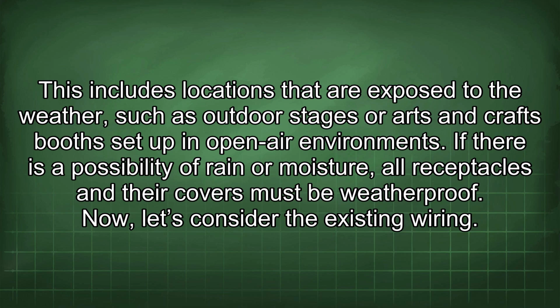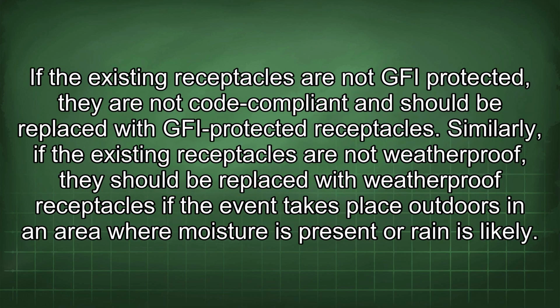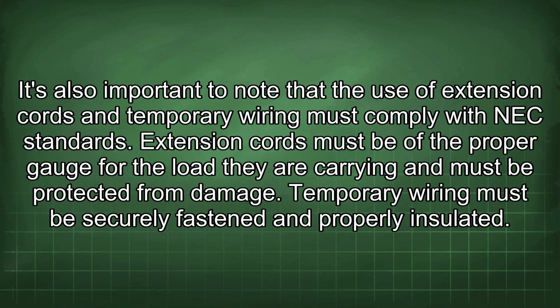Now, let's consider the existing wiring. If the existing receptacles are not GFI protected, they are not code compliant and should be replaced with GFI protected receptacles. Similarly, if the existing receptacles are not weatherproof, they should be replaced with weatherproof receptacles if the event takes place outdoors in an area where moisture is present or rain is likely. It's also important to note that the use of extension cords and temporary wiring must comply with NEC standards. Extension cords must be of the proper gauge for the load they are carrying and must be protected from damage. Temporary wiring must be securely fastened and properly insulated.